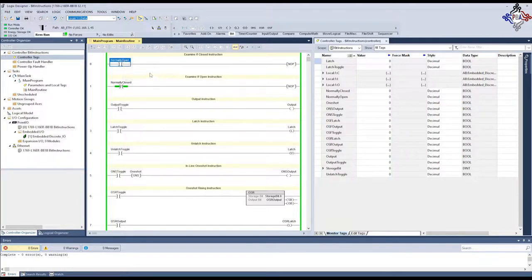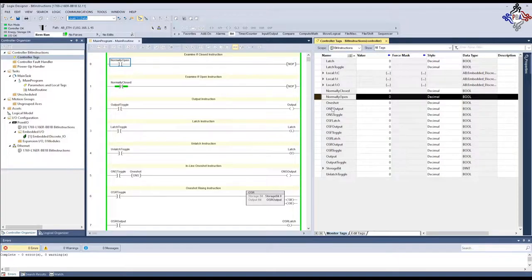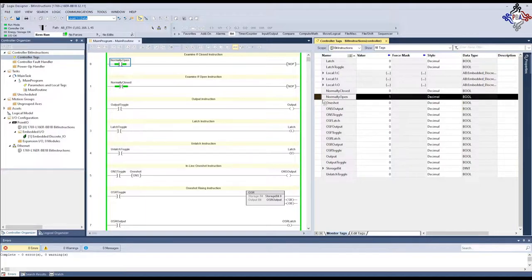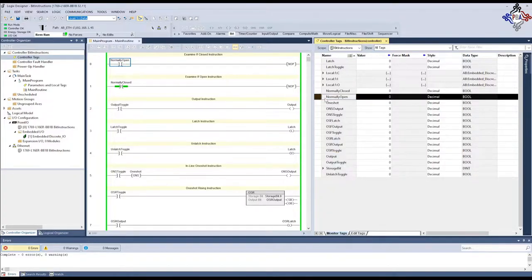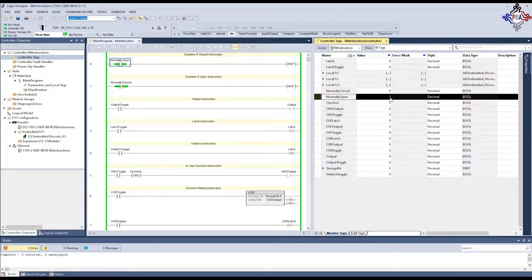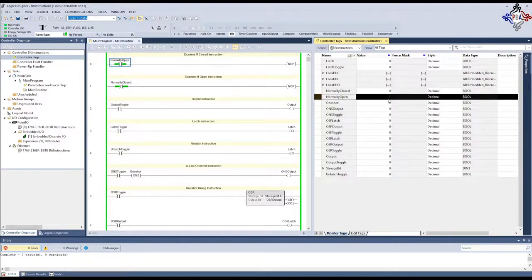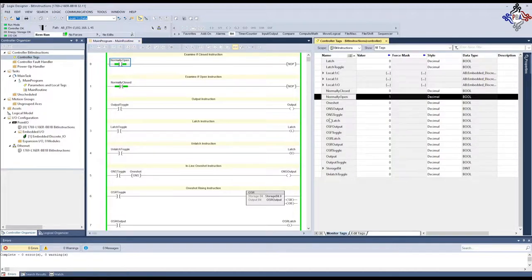If we come over here to our tag database, we find our normally open instruction, and I'm going to go ahead and toggle that on. To toggle, I use Ctrl T. It's a hotkey to use. You can also right click to toggle that bit on and off. Right now, our bit has a 1, meaning it's toggled on. And the examine if closed instruction is allowing the controller to scan through this. If we turn it off, the controller stops scanning that line. It stops examining it.